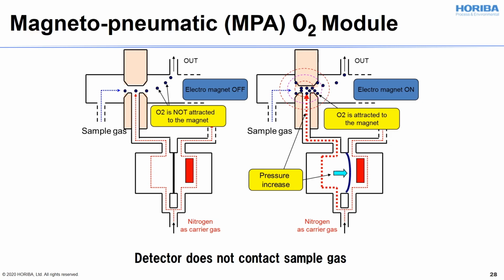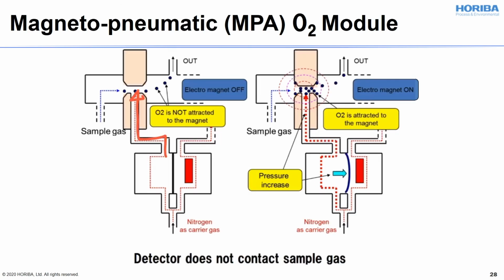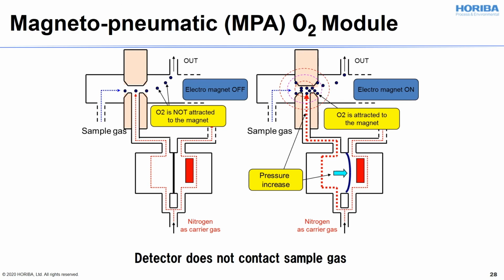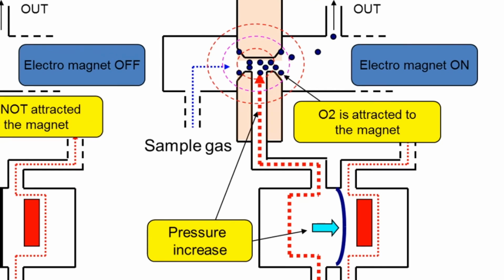With the electromagnet off, O2 is not attracted to the field. And in this area we feed carrier gas. So while the electromagnet is off, sample and carrier gas flow smoothly. When the electromagnet is on, O2 starts being attracted to the magnet, and this causes a pressure increase inside the chamber of the detector.